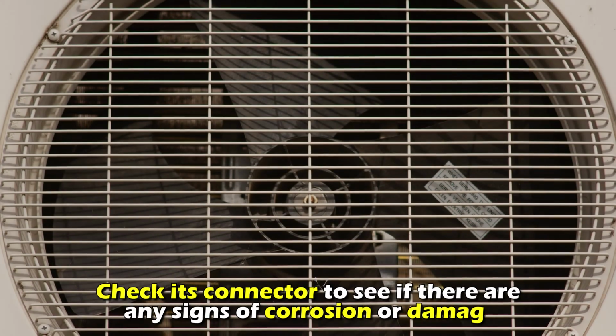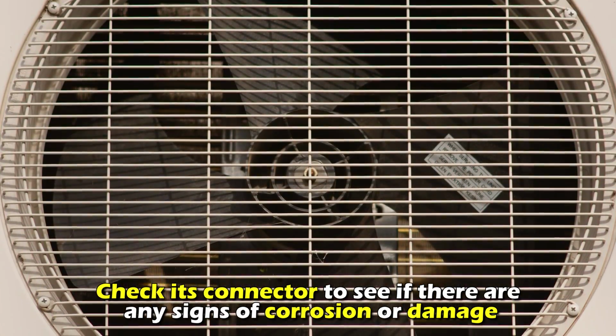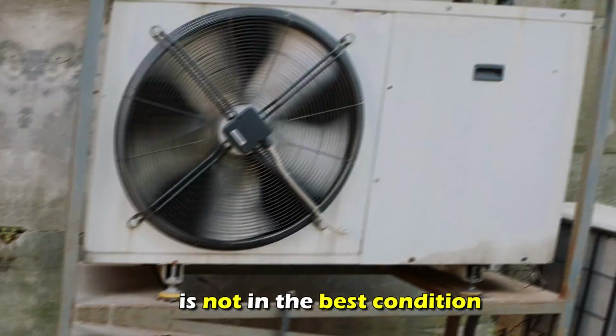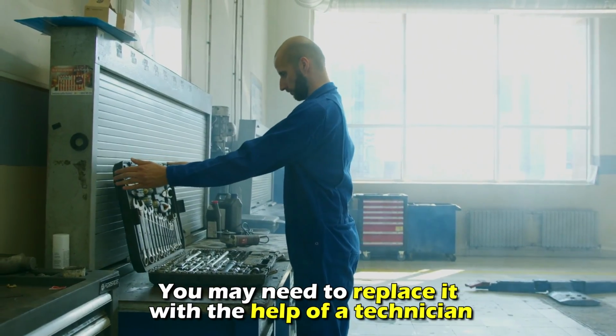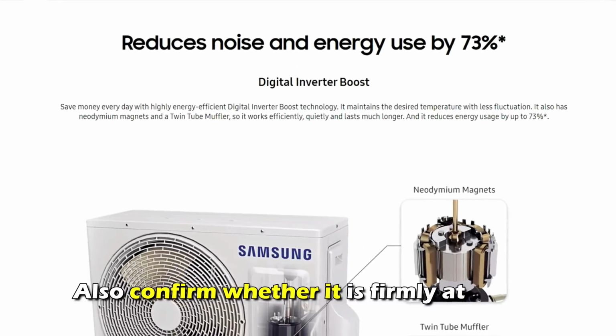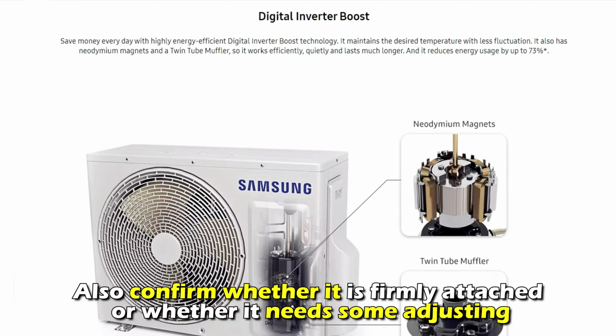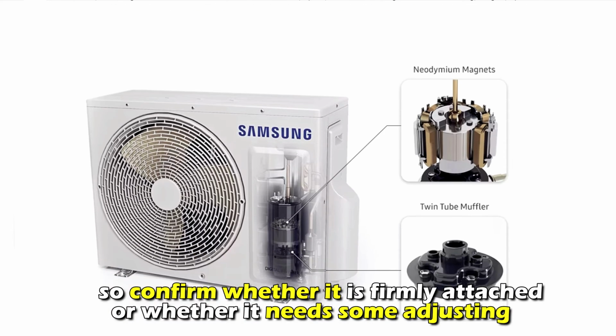Inspect the outdoor unit fan. Check its connector to see if there are any signs of corrosion or damage. If it's not in the best condition, you may need to replace it with the help of a technician. Also, confirm whether it's firmly attached or whether it needs some adjusting.